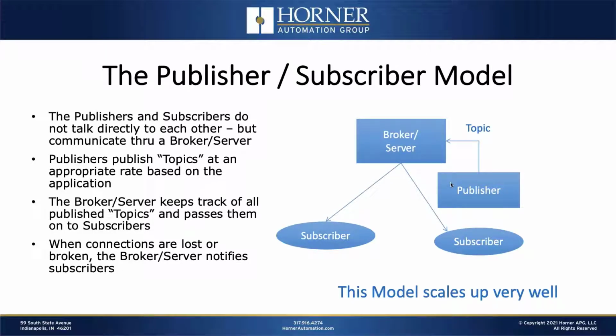Getting back to the publisher-subscriber model that has made MQTT popular among industrial type folks. What this does is it basically separates the objects that are exchanging data, it disconnects them from each other. So when you have Modbus TCP or something like that, or one of our other traditional industrial protocols, the devices that are sharing data with each other are permanently connected. In this publisher-subscriber model of MQTT, the publishers and subscribers don't talk to each other directly. Everything goes through the broker, which is also called a server, probably more commonly a server these days, but I'm going to use those two terms interchangeably.